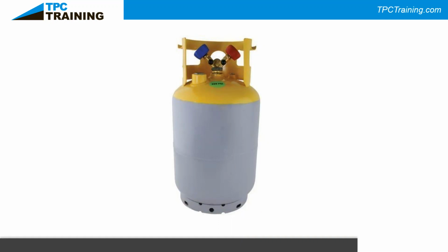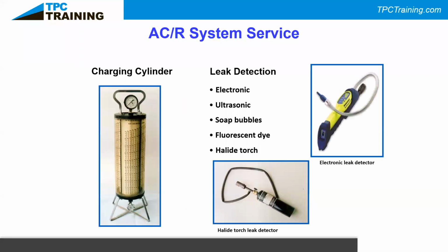If it does not fall anywhere on the pressure temperature chart, that means somebody mixed the refrigerant together. They didn't want to bother to take the time to see if it's R22 in there, and they mixed R22 and R410. What they did then was cause your company money to have to send it out and have it destroyed. So instead of getting a reward for saying, good job, now we got some R22, we can reuse the R22 by purifying it, we're not able to do that anymore.